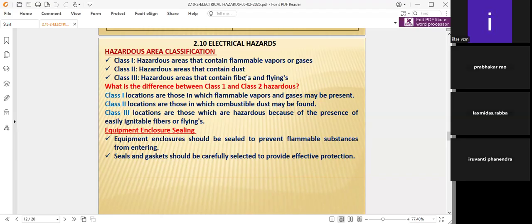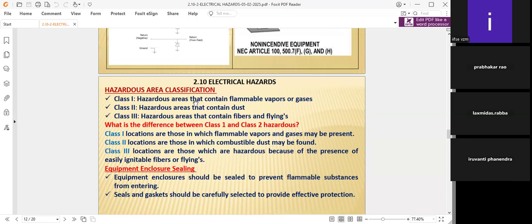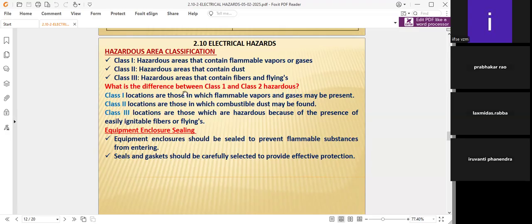These three classes are very important areas, and there is class 1 again. What is the difference between class 1 and class 2 hazards? Class 1 locations are those in which flammable substances, already told. Class 2 locations are those in which combustible dust may be found. Combustible dust takes oxygen from the atmosphere and burns immediately. Or the dust accumulates on the circuits, the circuits get heated, the dust is ignited, and fire will happen in the electrical circuits itself.